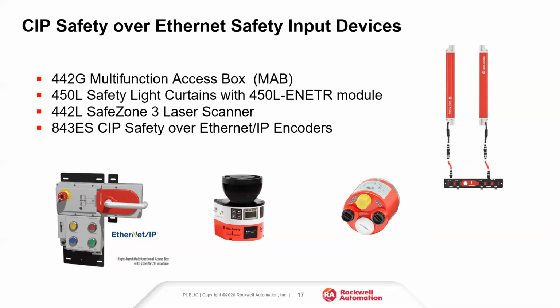That's usually pretty convoluted, with a lot of wiring that has to go back to regular safety monitor relays or even Compact GuardLogix to the safety I/O. But with the 442G multifunction access box with CIP Safety over Ethernet, you're simply supplying power and then the Ethernet connection. And like Mark was mentioning earlier, all the design and diagnostics are pulled up through the add-on profiles and the instructions in Studio 5000. So it makes for a very clean installation, as well as ease of installation and troubleshooting, with a lot fewer wires that you have to run down and understand what kind of issues you may be running into.